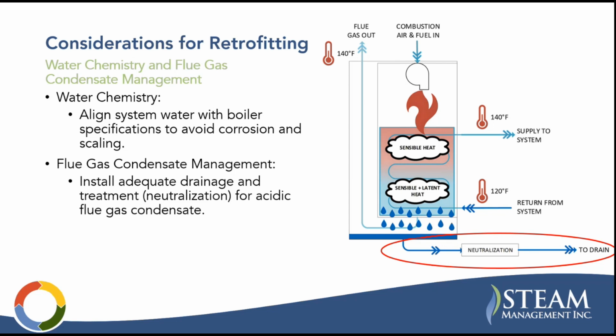Water chemistry and flue gas condensation management. I just want to mention the water chemistry. You want to check what the manufacturer's recommendations are and make sure that you're complying with that. As far as flue gas condensation management, we're talking about that condensate coming out of the flue gas that needs to be neutralized before you go to drain. Something to think about and something to put in your maintenance plan, if you're going to run these things.